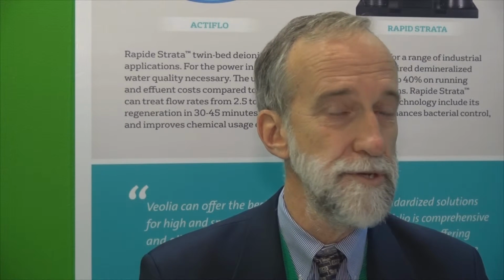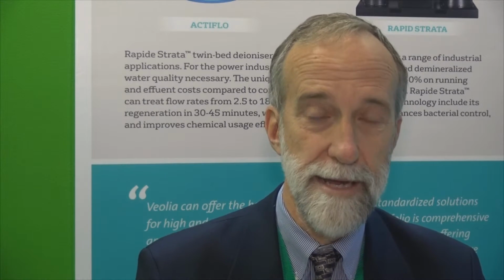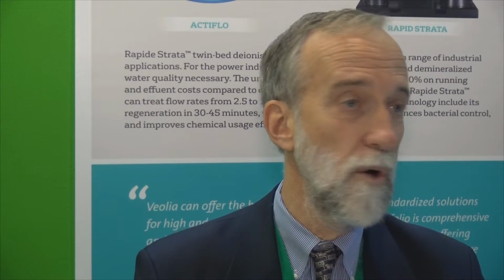The real benefit in the power industry for the disc filter in general is for cooling tower makeup or side stream filtration. It has tremendous benefits over conventional side stream media filtration—it's easy to operate, compact, and easy to install. We're seeing a lot of trending use for gray water or reclaimed water, treating it with a Hydrotech disc filter for cooling tower makeup. Very inexpensive, so that's a trend all over the globe.